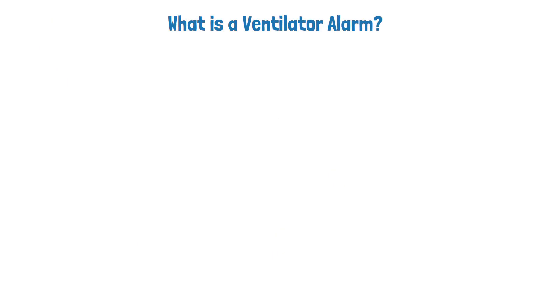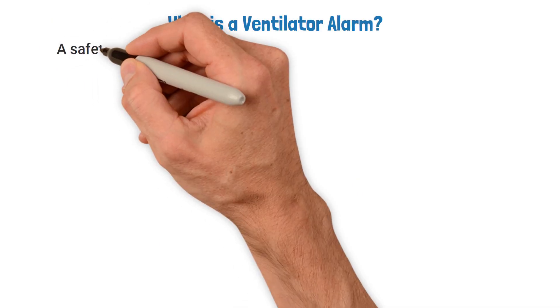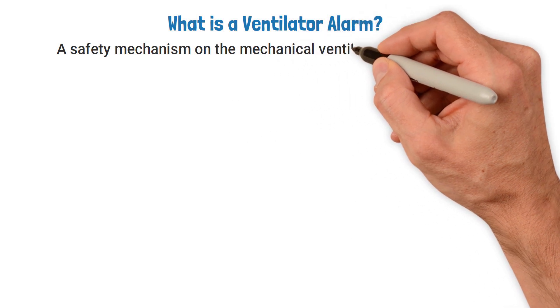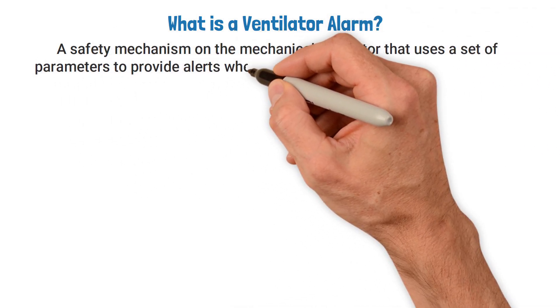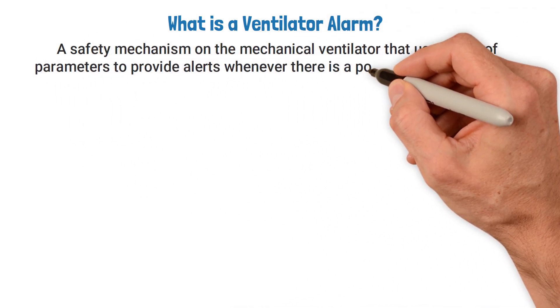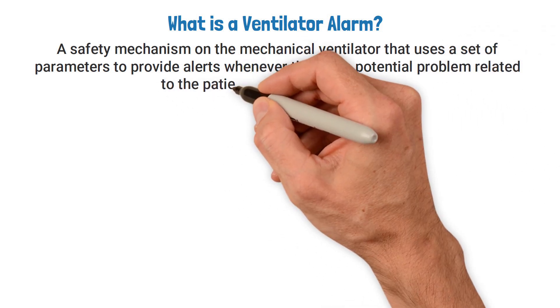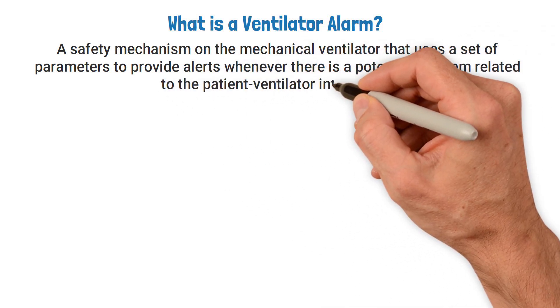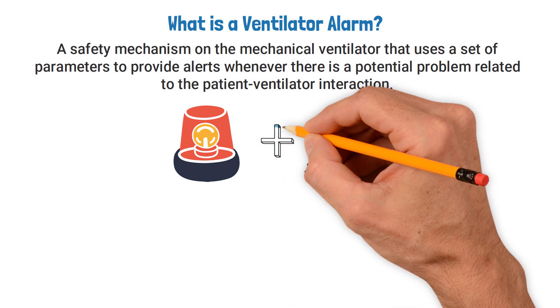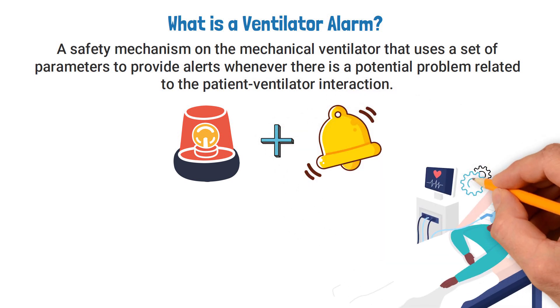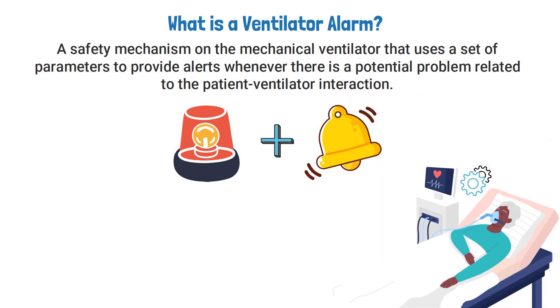A ventilator alarm is a safety mechanism on the mechanical ventilator that uses a set of parameters to provide alerts whenever there is a potential problem related to the patient-ventilator interaction. The alarms can be visual, audible, or both, depending on the ventilator setting and the patient's condition.